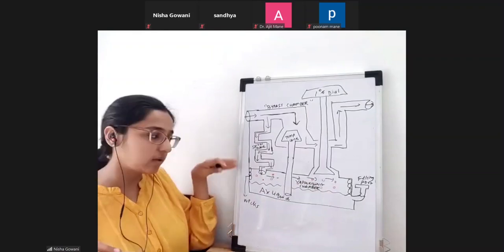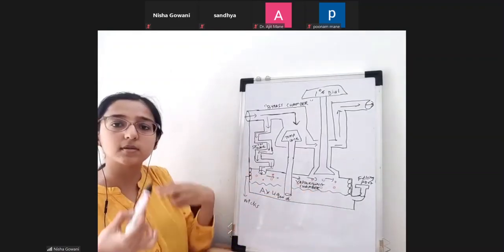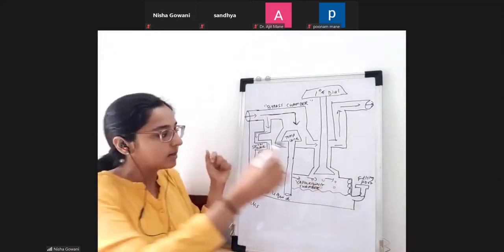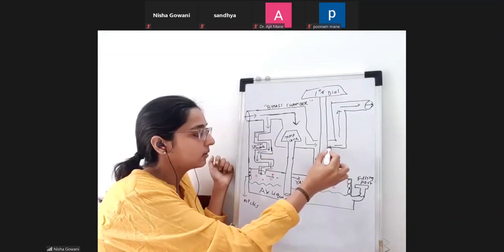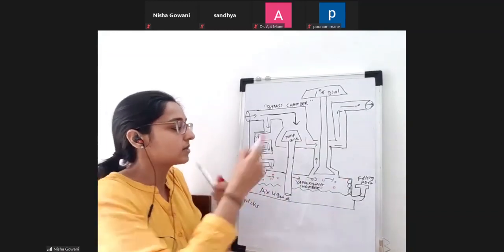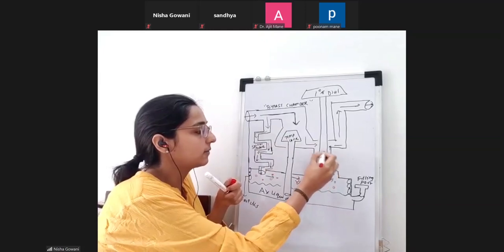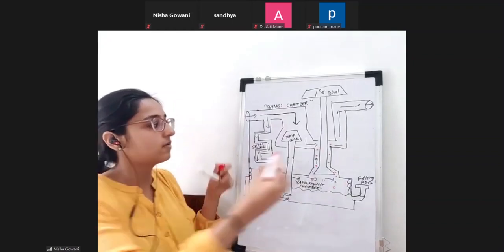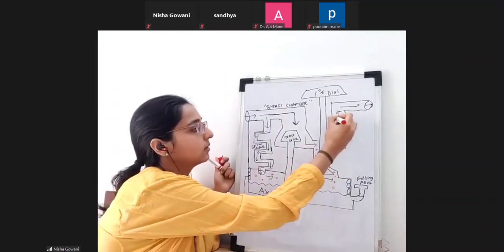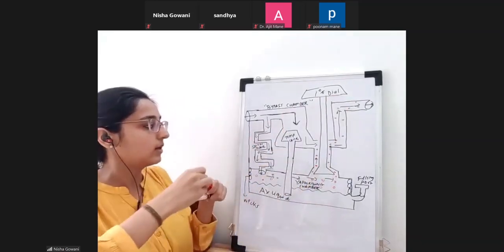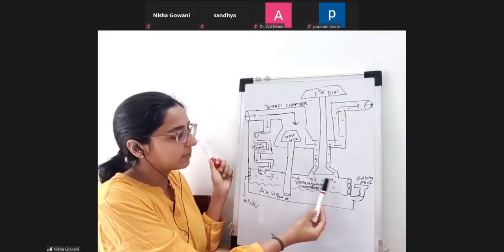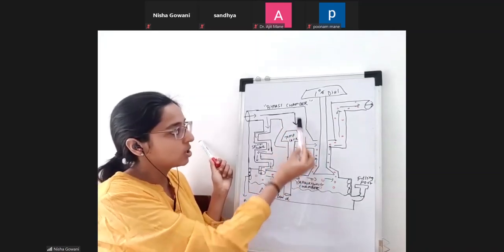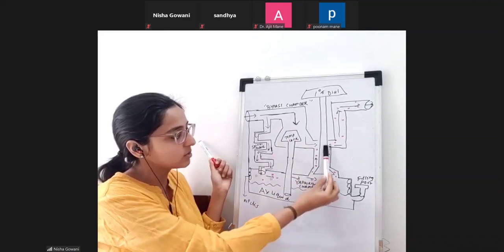While traveling over the vaporizing chamber, it is picking up the vapors. The oxygen nitrous is picking up the isoflurane vapors. Then it will go up. The gas, O2 nitrous, is carrying the vapors along with it. It is exiting the vaporizing chamber along with the vapors. Now this gas, which is carrying the vapors, is joining this gas, which does not carry the vapors. So this bypassed gas will join the gas which is carrying the vapors.